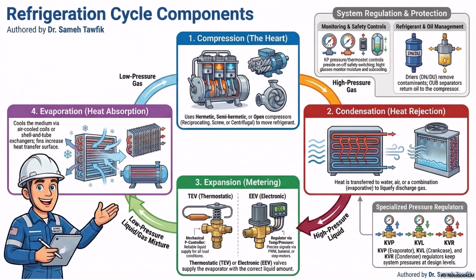So if they just loaded 10,000 tons of hot bananas into the hold, the evaporator is going to absorb a massive amount of heat and boil off a gargantuan tidal wave of gas very quickly. And all that gas rushes toward the compressor. Exactly. If it all hits at once, the compressor motor will overload and literally burn out trying to pump it. Oh, I see. The KVL senses that incoming tidal wave, pinches the line, and only feeds the compressor exactly the volume of gas it can safely swallow. Wow. So the KVP protects the evaporator from starving and freezing, and the KVL protects the compressor from gluttony and burning out. That's a great way to summarize it.